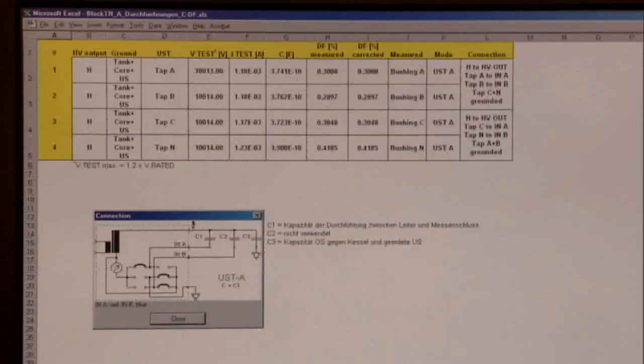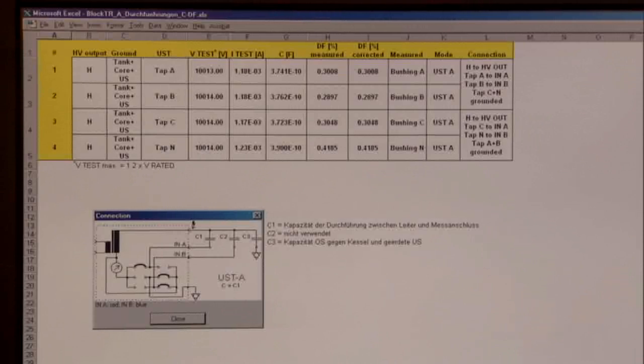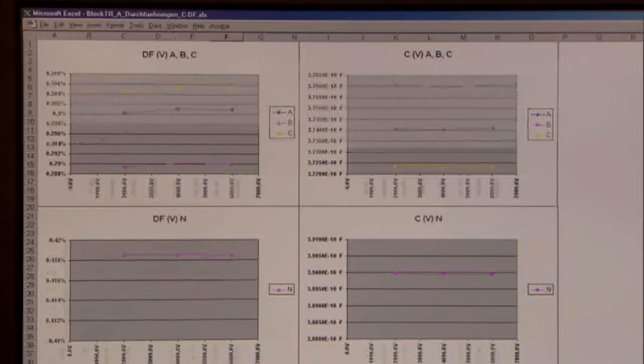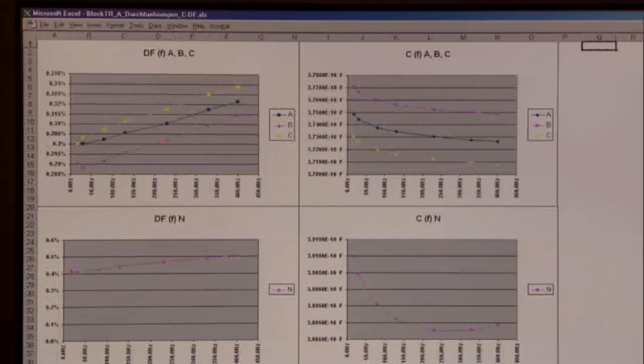Here we see the results for capacitance and power factor or dissipation factor at power system frequency, showing the relationship between the power factor or the dissipation factor and the capacitance of the high voltage bushing, plus the dependency between the power factor or the dissipation factor and the frequency.